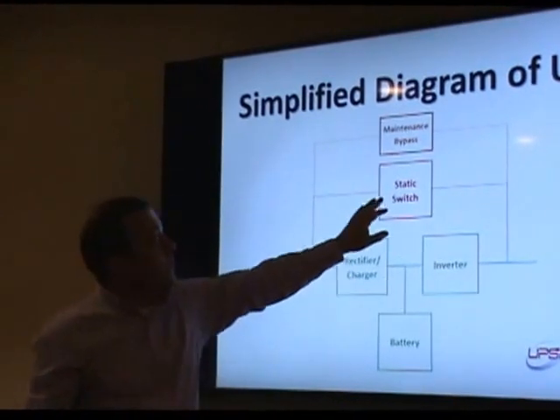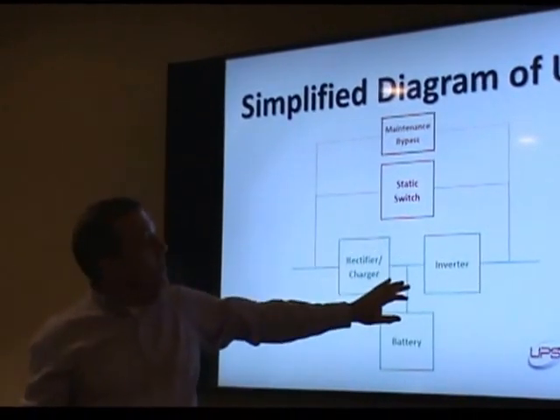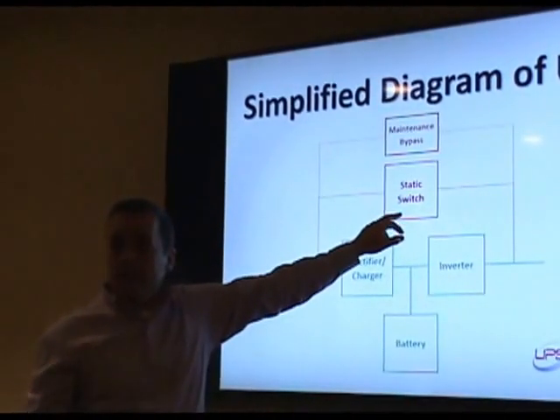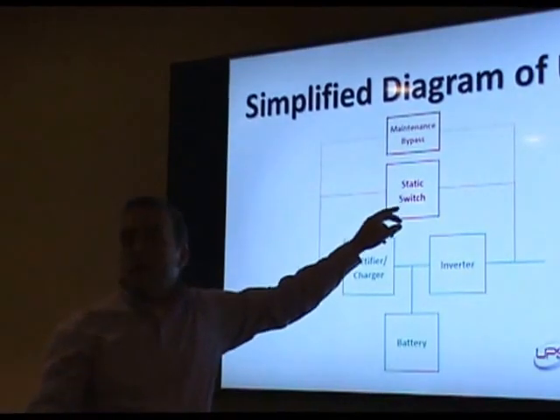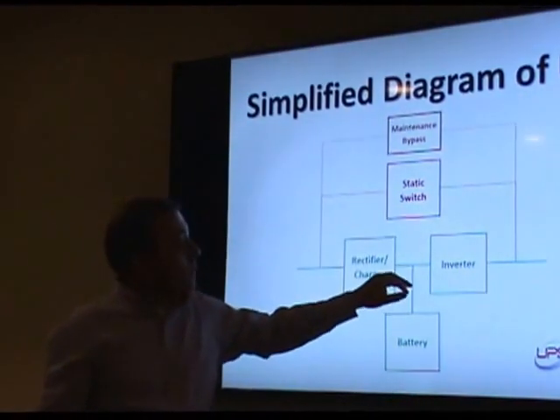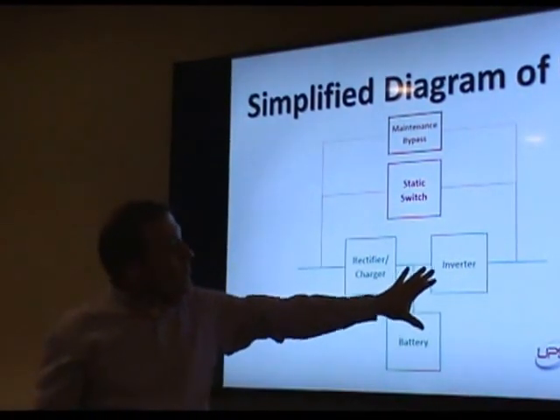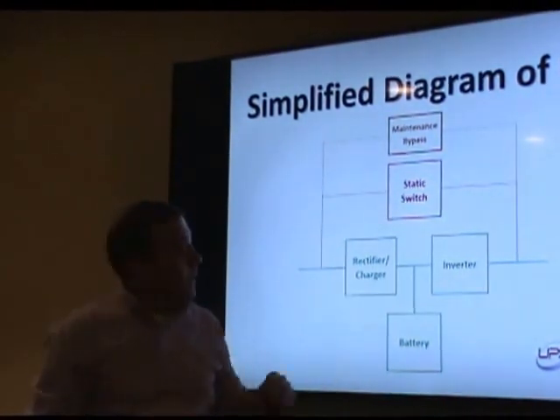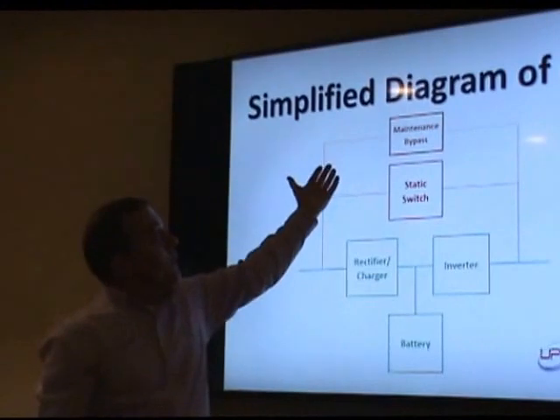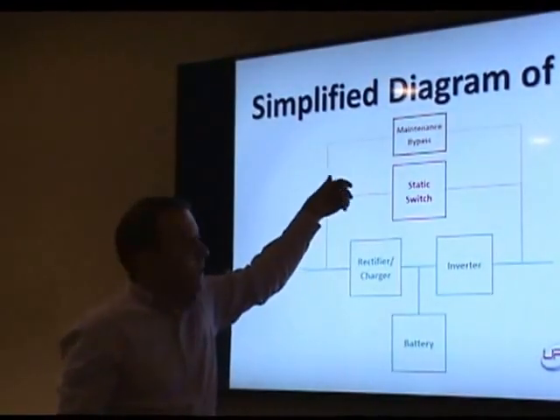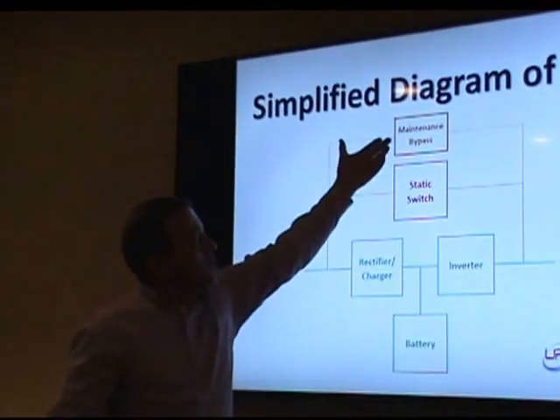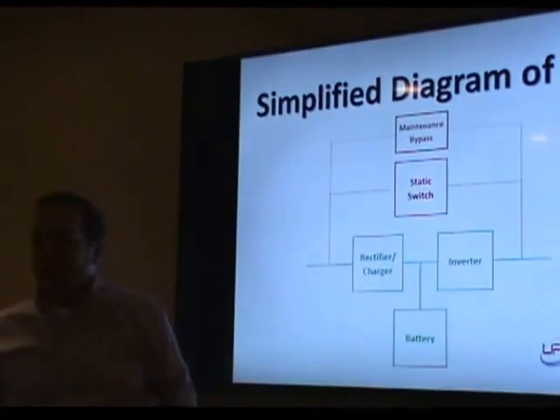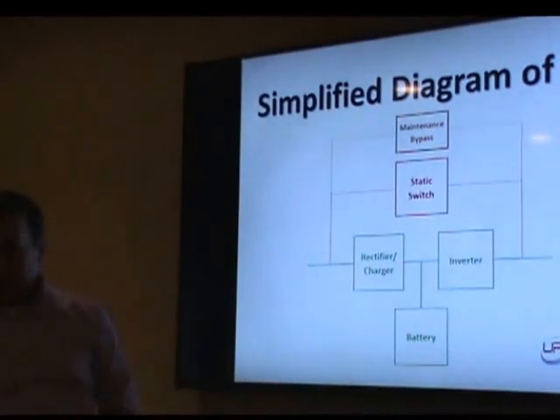In the event that there's an issue with the UPS and it has a failure, it has a little built-in static switch, and it will transfer from UPS right over to utility power. In the event you have to do maintenance, there's another switch outside of that where you can actually close this switch and pull the whole UPS out and replace it if you had to.